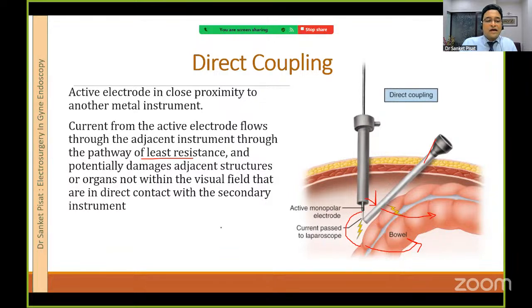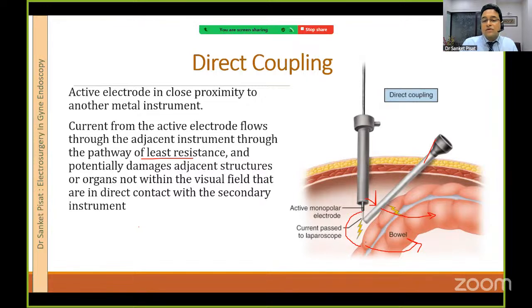And the problem for us is that these adjacent structures are not in the field of view. So you can see that if I'm going to be operating on this patient, my field of view is going to be restricted only here. And I may not see that this return electrode is causing a burn at this point and going back into the parent machine. So the injury is caused to adjacent structures not within the visual field or in direct contact with the secondary instrument.